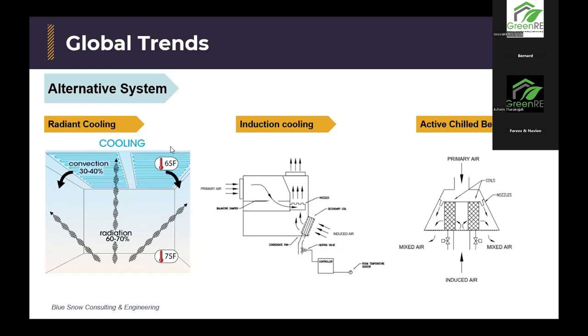Then you have induction cooling. Induction and displacement cooling are pretty much almost the same. Induction cooling can be the underfloor cooling. It's also very energy efficient. All these alternate systems are very energy efficient. Underfloor cooling is energy efficient in the sense that it uses a form of natural convection plus forced convection, because you're blowing the cool air from beneath, and we know from the movement of air, hot air goes up, cool air stays below. So because the air is coming from below, it's not very strong, it's just very mild, and it kind of naturally convects itself in the cool space. So it's a good design. I've seen a couple of banks use it as well.